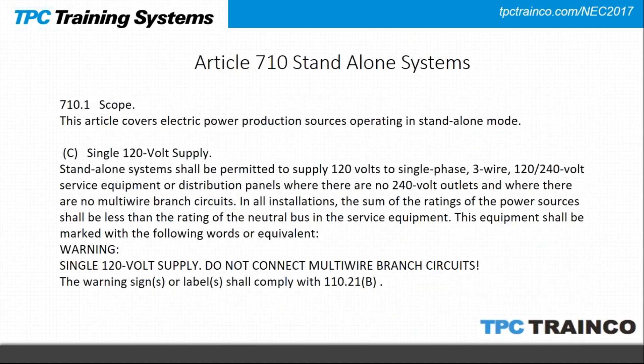Article 710 is for a standalone system — a much smaller system. It's going to supply a single 120-volt, single-phase supply. Picture a large solar panel on the side of the road supplying a couple of flashing lights. That's a standalone system, not connected to anything else, supplying a relatively small load.